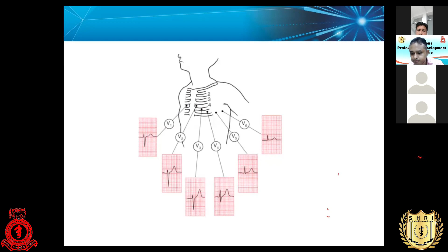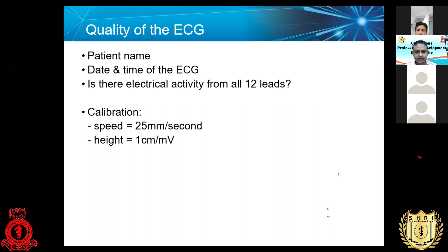And document the name, age, the date and time of the ECG that you have taken, and check whether all the 12 leads are recorded properly. Your machine has to be calibrated at 25 millimeters per second, the speed, and the height should be calibrated at 1 centimeter per millivolt. If you change these, we will get abnormal ECGs, which are pseudo abnormalities that we are going to record. So make sure that your calibration is correct, with the speed at 25 millimeters per second and the height at 1 centimeter per millivolt.